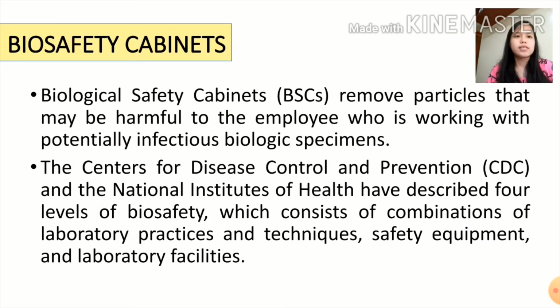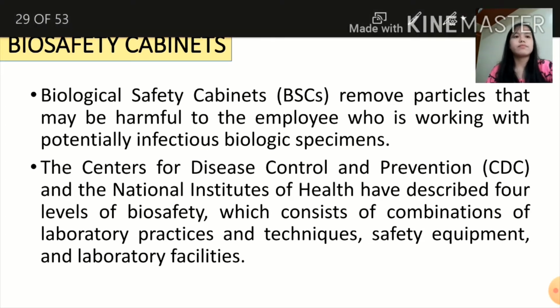Biosafety cabinets remove particles that may harm the employee who is working with potentially infectious biologic specimens. The Centers for Disease Control and Prevention and the National Institutes of Health have described four levels of biosafety, which consist of combinations of laboratory practices and techniques, safety equipment, and laboratory facilities.